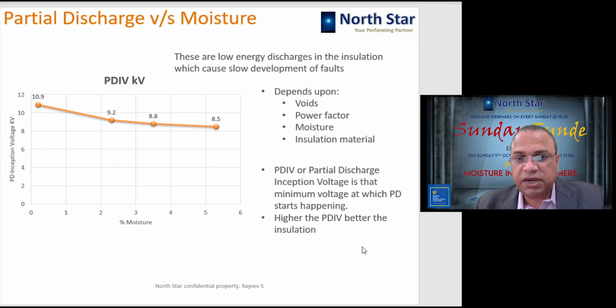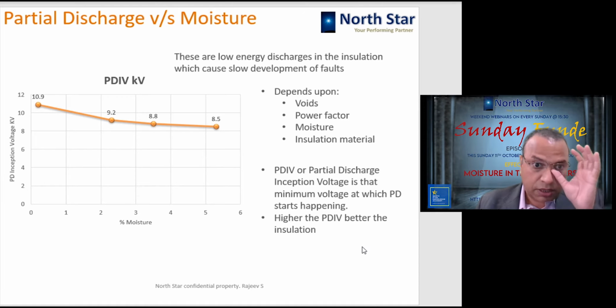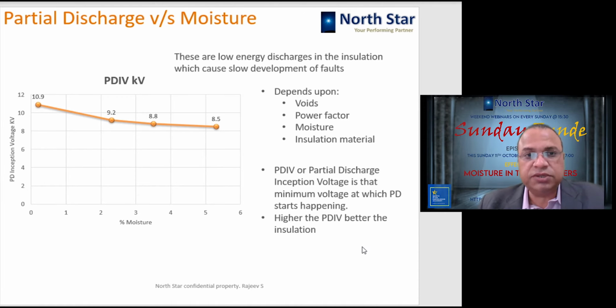The equipment, typically your current transformers, potential transformers, and oil impregnated paper bushings, OIP bushings, are more susceptible to failure because of this phenomenon, because they are very compact, very little quantity of oil is there, and because of failure of oil seals, leakage happens and moisture goes inside. Oil gets released because of leakage, so oil quantity comes down. So the paper of this equipment, which should remain immersed in the oil, gets exposed to the air, partial discharge happens in this bushing, and these components fail. So that is why bushing failures and CT/PT failures are very high compared to transformer failures. Okay, so this is a very important aspect to be considered while doing the O&M of the transformers.